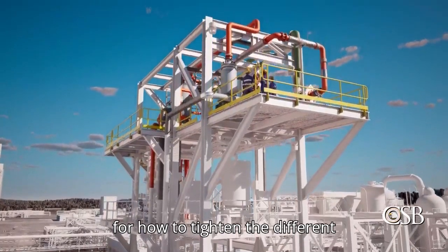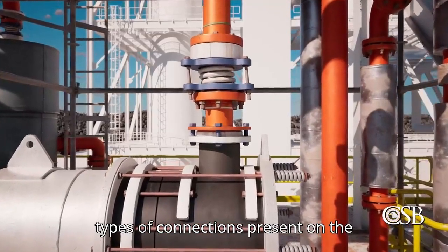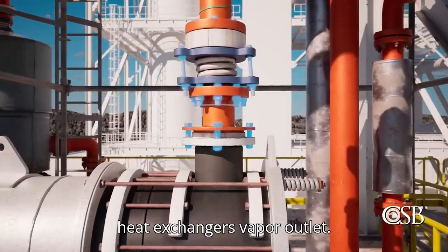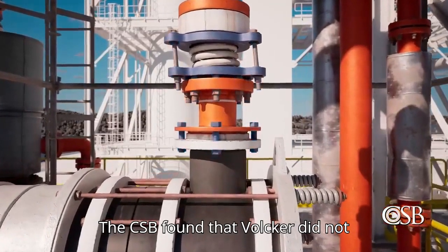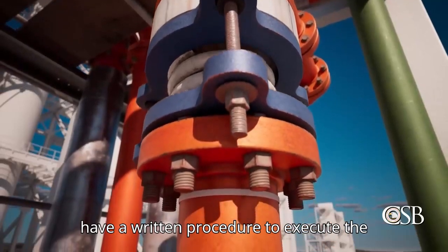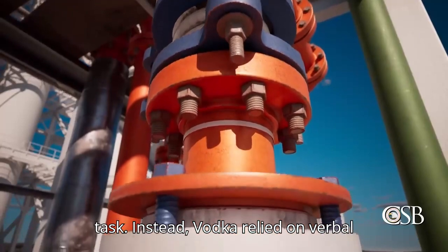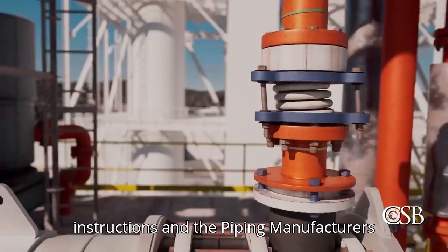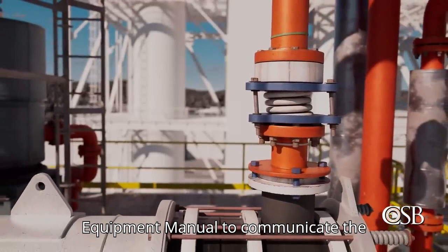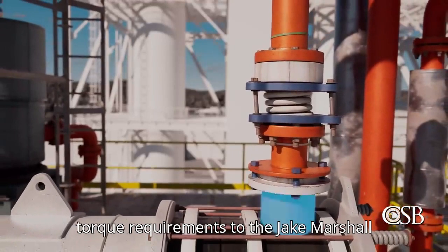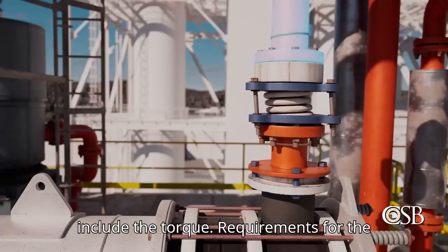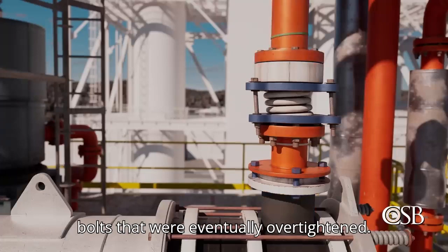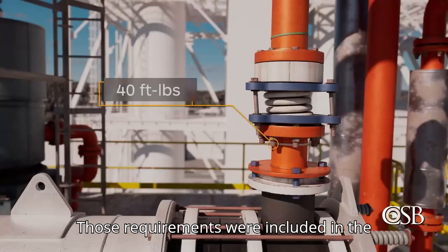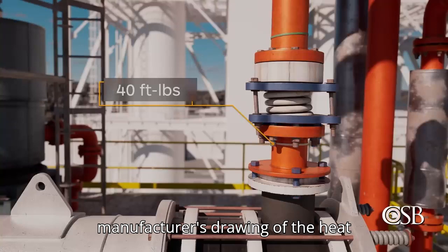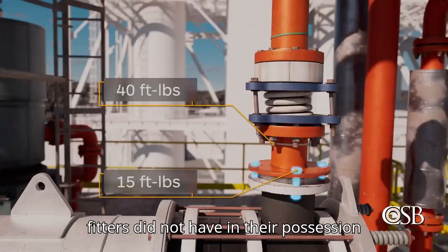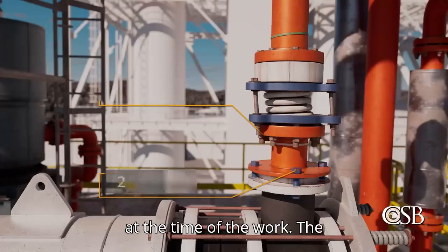These should have included clear instructions for how to tighten the different types of connections present on the heat exchanger's vapor outlet piping. But the CSB found that Wacker did not have a written procedure to execute the task. Instead, Wacker relied on verbal instructions and the piping manufacturer's equipment manual to communicate the torque requirements to the Jake Marshall contractors. The manual, however, did not include the torque requirements for the bolts that were eventually over-tightened. Those requirements were included in the manufacturer's drawing of the heat exchanger, which the Jake Marshall pipe fitters did not have in their possession at the time of the work.